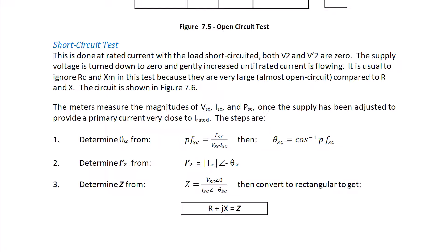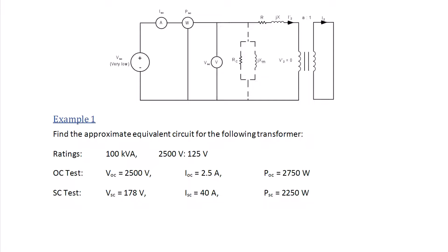The circuit is shown in Figure 7.6, and the following steps are used after finding the magnitudes of VSC, ISC, and PSC. Once the supply has been adjusted to provide a primary current very close to I-rated, the steps are to determine the short-circuit angle PFSC equals PSC over VSC ISC, where theta SC is the arc cosine of the power factor. Determine I2 prime, which is the magnitude of ISC at the angle negative theta SC. And determine Z by using VSC angle zero over ISC angle negative theta SC, and then convert that to rectangular form to get Z equals R plus jX.